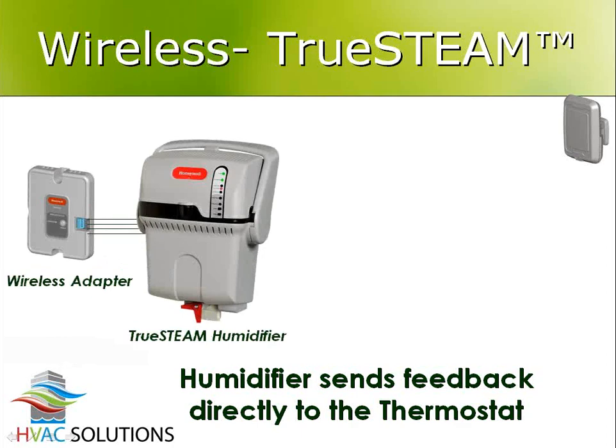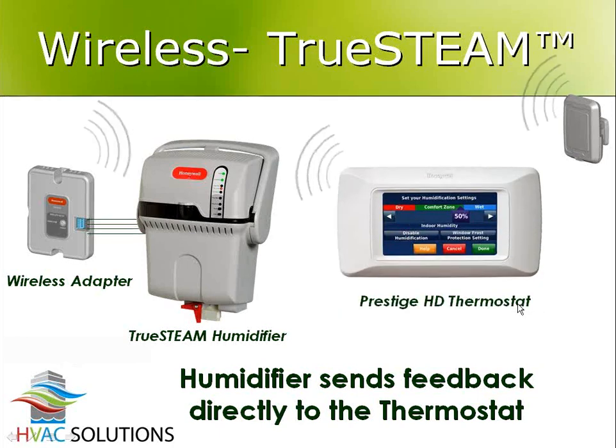Now, just like with the furnace on the FocusPRO stats, the wireless receiver adapter has to hardwire to the furnace. Well, in this case, the wireless adapter wires to the humidifier. So just keep that in mind. So there's wires between the adapter and the humidifier, and those can be sitting right next to each other downstairs at the furnace. And that adapter talks wirelessly to the stat, and the outside air sensor talks wirelessly to the stat. And sometimes you might want to reset the humidity set point based on outside air. So all those things work together without any additional wires between them. But the thermostat still hardwires to the furnace.